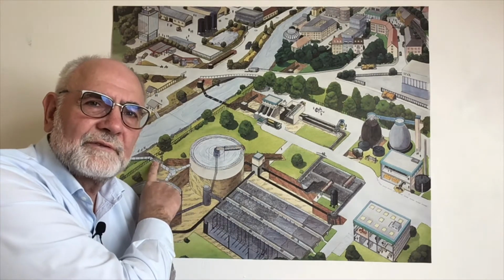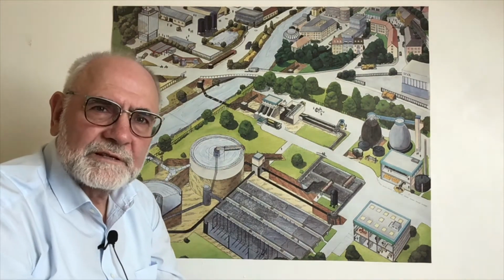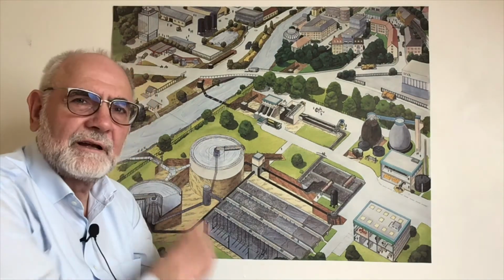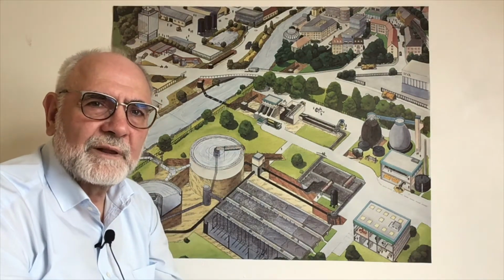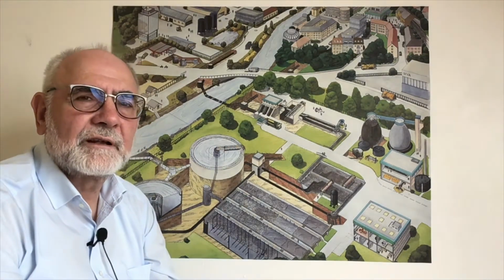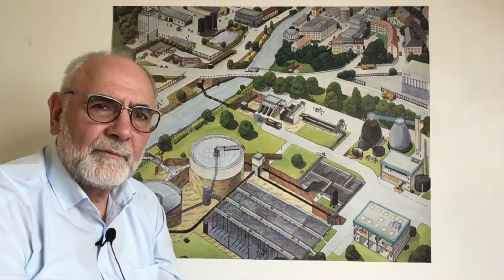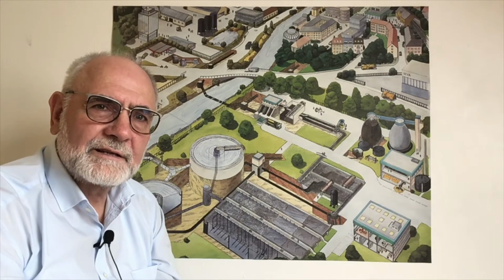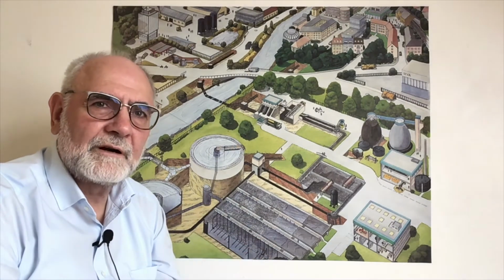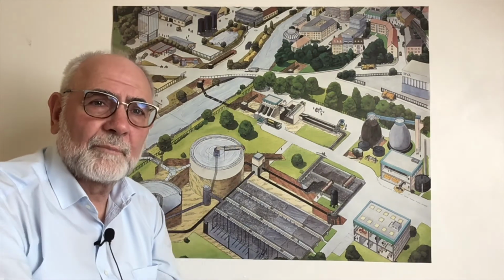That's where the control of the government comes. So every week, more or less, for big wastewater treatment plants, the upper water authority comes, takes samples, and every wastewater treatment plant has a permission, and they have to stay within the permission. The sampling is an on-spot sampling. That means within 10 minutes, samples are taken and then brought to the lab and then analyzed. And 4 out of 5 measurements must be lower than the permission limits. If that is not the case, then this operator has to pay.